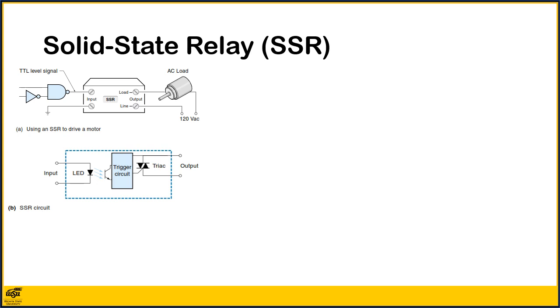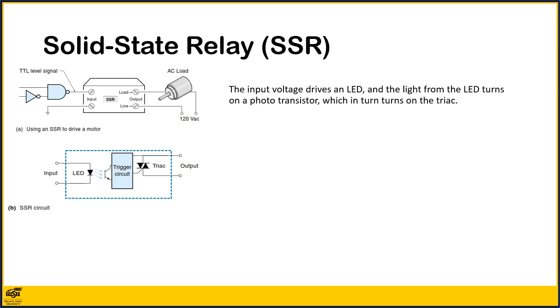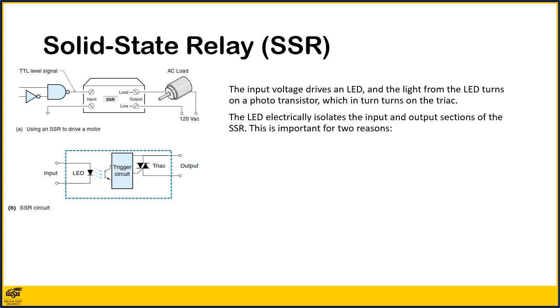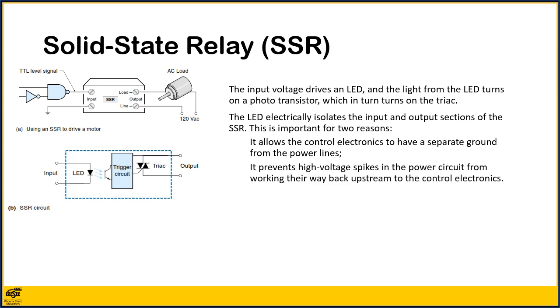Figure B shows a block diagram of the interior of an SSR. The input voltage drives an LED, a light-emitting diode, and the light from the LED turns on a phototransistor, which in turn turns on the TRIAC, a solid-state switching device discussed later in this chapter. The LED electrically isolates the input and output sections of the SSR. This is important for 2 reasons. First, it allows the control electronics to have a separate ground from the power lines. And second, it prevents high voltage spikes in the power circuit from working their way back upstream to the more delicate control electronics.